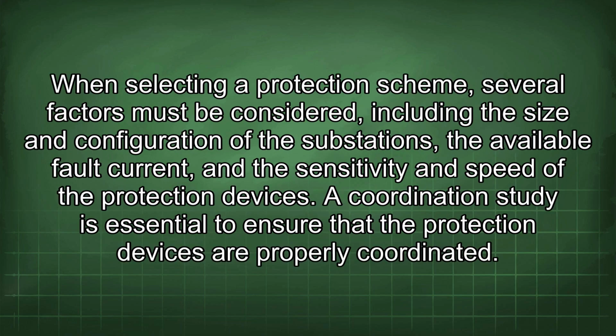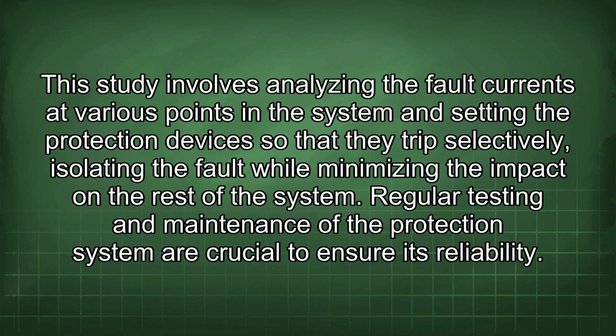When selecting a protection scheme, several factors must be considered, including the size and configuration of the substations, the available fault current, and the sensitivity and speed of the protection devices. A coordination study is essential to ensure that the protection devices are properly coordinated. This study involves analyzing the fault currents at various points in the system and setting the protection devices so that they trip selectively, isolating the fault while minimizing the impact on the rest of the system.